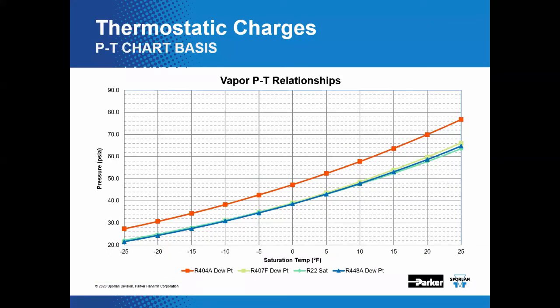Why are the thermostatic charges for 407F and 448A the same and the same as R22? Why are they different from 404A? Well, we can tell much about what we need to know from the pressure temperature chart that we now have displayed. Since superheat is calculated using dew point conditions, it follows that superheat is also controlled from the dew point temperature. If we plot the dew point curves of these refrigerants over a range of low and medium temperature evaporator conditions, we find that R404A's dew point is several PSI higher and that of R407F and 448A closely follow the saturation curve of R22. That's what's depicted right here.